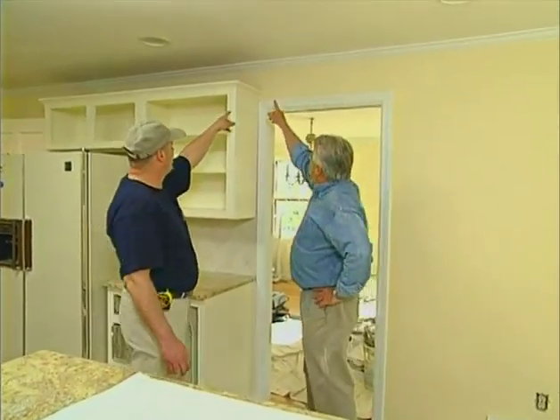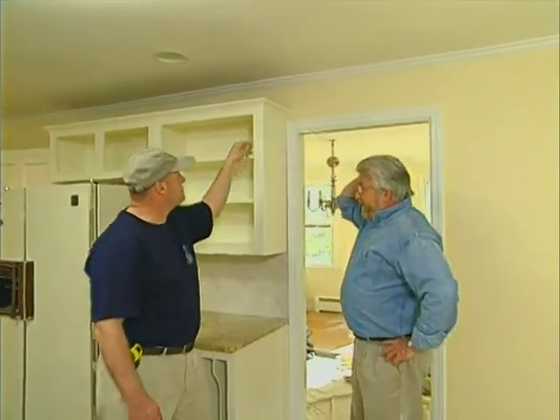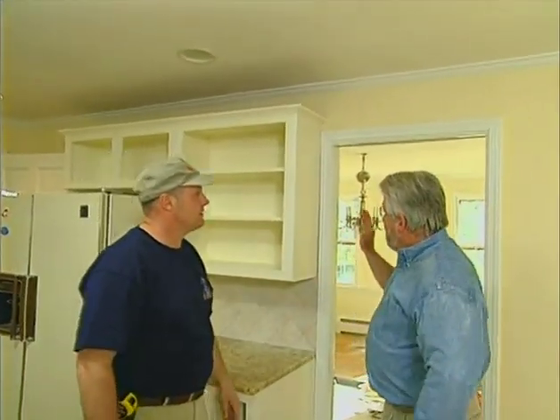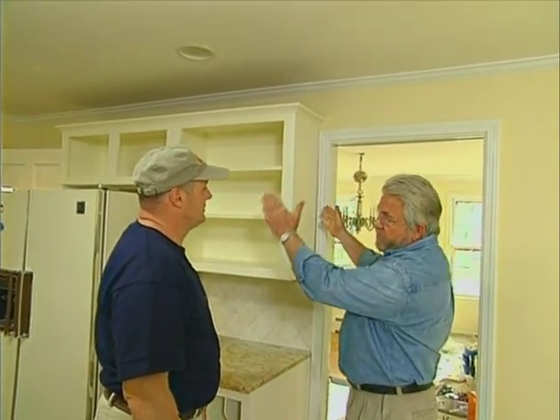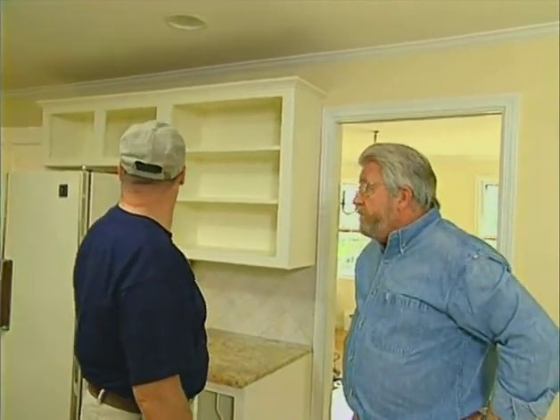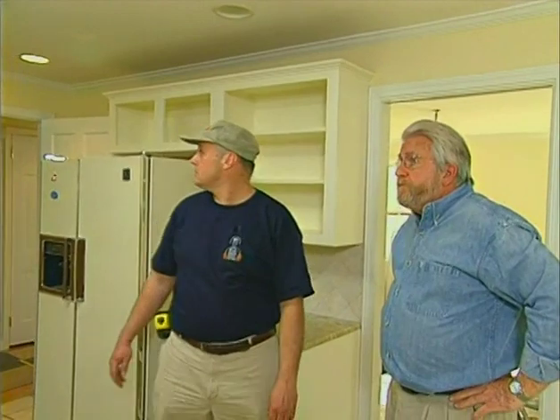Well, for example, in the kitchen, in fact, we have one going in right here above the cabinet. Right up here? We have a horizontal sidewall about 6 inches below the ceiling. You know, something I didn't tell you the other day when you were here. I think I'm going to take this out, and I'm going to be building a pantry in here, which is going to stick out probably this far. It might go up to the ceiling. Is that going to be a problem for you? Yes, that will be a problem. We're going to have to look into another possible location for putting that sprinkler head in the kitchen.